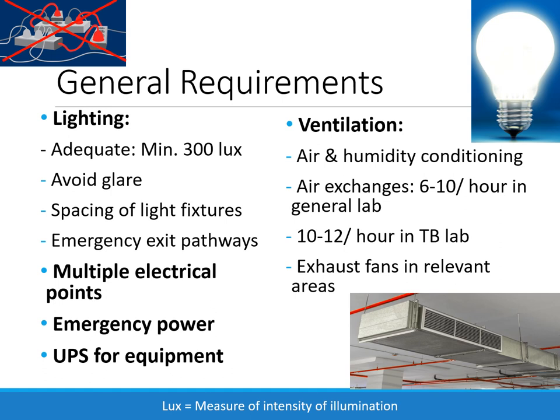Power supply: there must be multiple electrical points so that all equipment, including microscopes, may be connected directly to an electric point, avoiding the need for extension cords and multiple pins into one electric point. There must be a provision for emergency power supply in case of power outages, and emergency exit pathways and signs must be supplied by this emergency line. The laboratory must also have a UPS for the equipment.